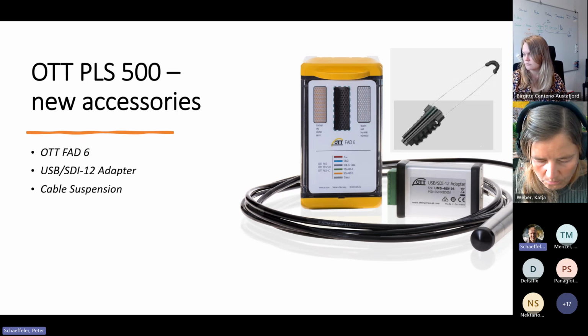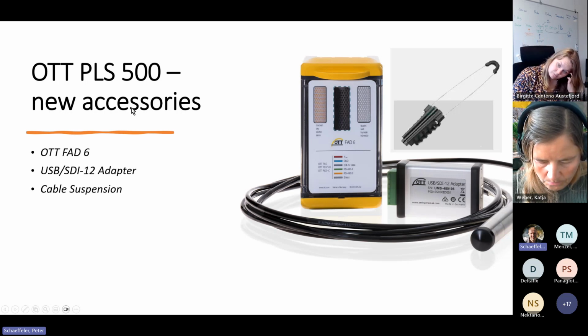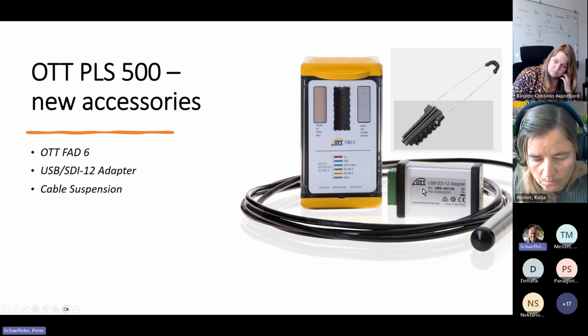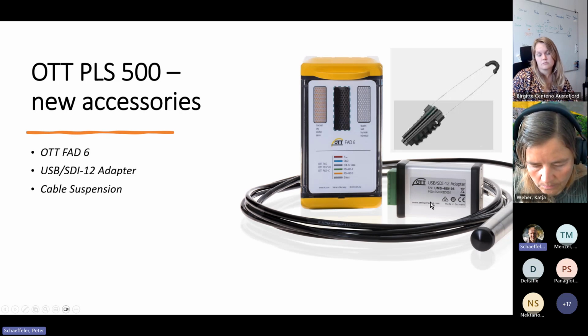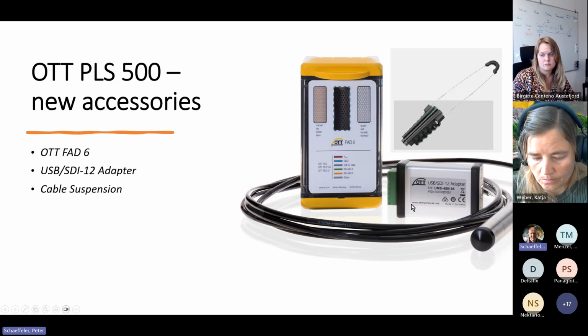Then we have a new USB/SDI-12 adapter. You might know we've had this product for a long time, but this is also a new one, designed during the PLS 500 development. There are some new features - in the software, all the templates for our sensors are there, and the biggest improvement compared to the old adapters is that it's powered by USB. So you connect it to your laptop, then connect your PLS 500, RLS, or whatever - you don't need to power the sensor separately, it's powered via USB. That makes it easier to do a quick run on a sensor, connect to your laptop, check the serial number, do firmware updates, and so on. This is also a new device launched together with the PLS 500, but can be used with all OTT HydroMet SDI-12 products.